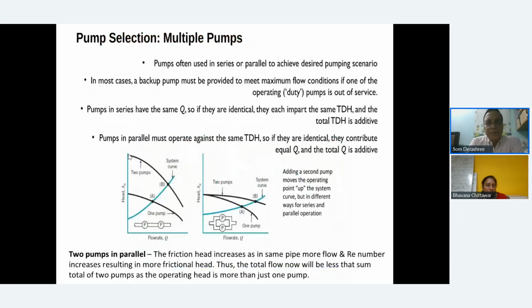Now, we have a choice. Let's say we can have multiple pumps. With multiple pumps, there are two choices. You can have them in series or you can have them in parallel. With pumps in series, the head will increase, because the flow will remain the same. Whatever is sucked here is pumped here, it's sucked here, it's pumped here. So the Q is the same. For every Q, you will have a head that is almost double the head of a single pump.